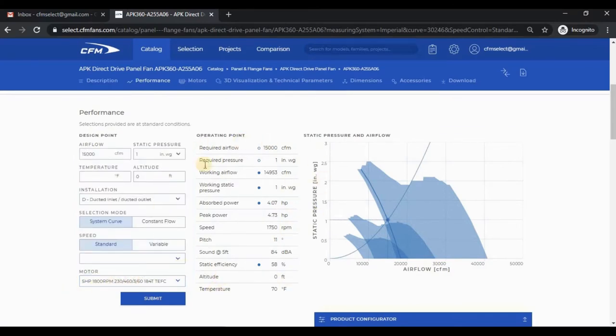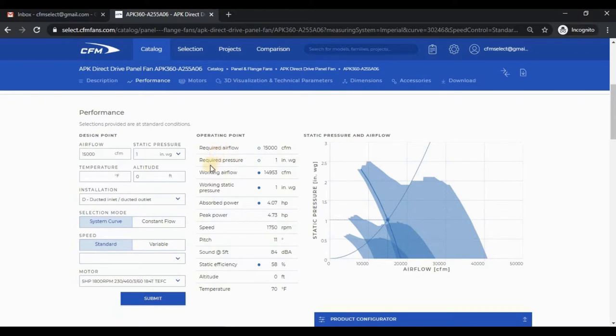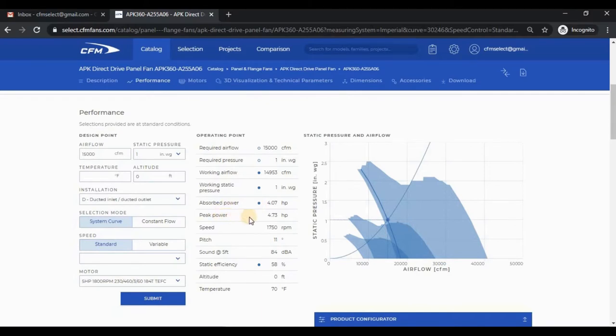The operating point information is summarized in this section. The required air flow and pressure are the inputs, and the working air flow and pressure are the outputs. The absorbed power is the power required at the operating point. The peak power is the maximum power along the fan curve.